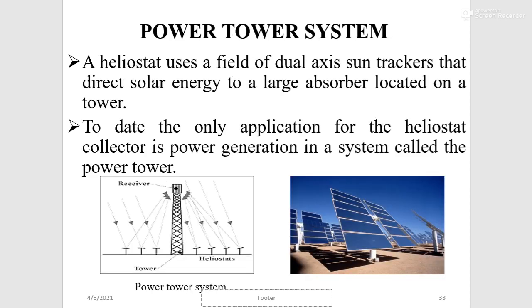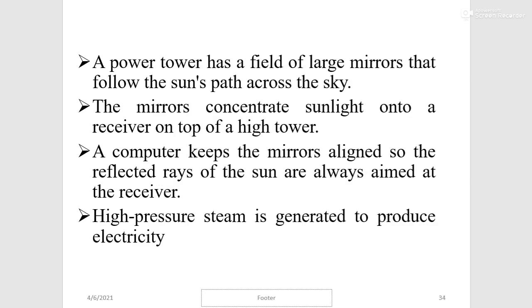A power tower system uses a heliostat field of dual-axis sun trackers that direct solar energy into a large absorber located on a tower. A power tower has a field of large mirrors that follow the sun's path across the sky, concentrating sunlight into a receiver on top of a high tower. A computer keeps the mirrors aligned so that the reflected rays of the sun are always aimed at the receiver, and high-pressure steam is generated to produce electricity.